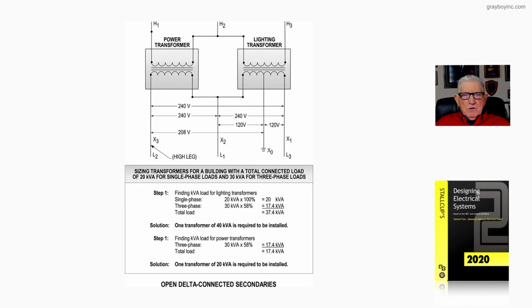So, if you should review transformers on a pole, or not necessarily review, just look at them, you notice that if you see a very large transformer and one smaller, that's open delta. It's pretty easy to see. Now, when you get three transformers on a pole, they could be Y or they could be a closed delta configuration. But reviewing these connections, as you see, and these drawings, you can determine very quickly exactly how the transformer is connected. So this figure 20-2B is simply showing how to size open delta transformers when you connect them in an open delta configuration.